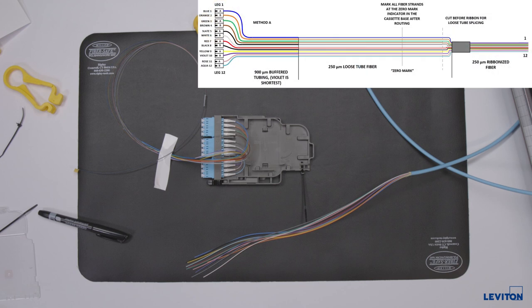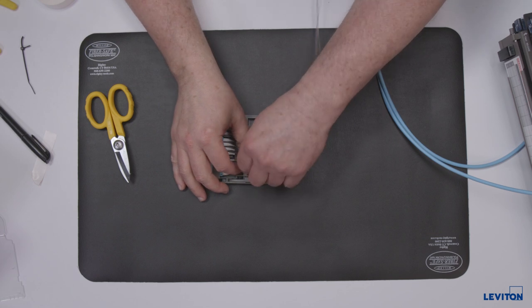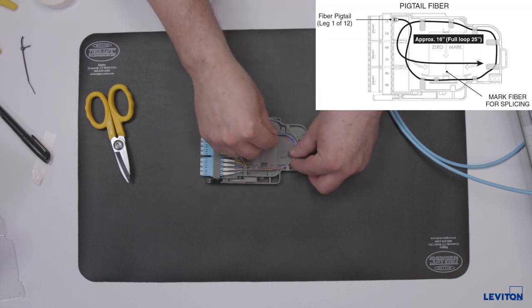The pigtail is designed to allow for both ribbon and single fusion splicing. This will determine the routing and marking steps of the pigtail. If terminating single fibers, cut the fibers before the black tape and ribbonized area of the assembly.